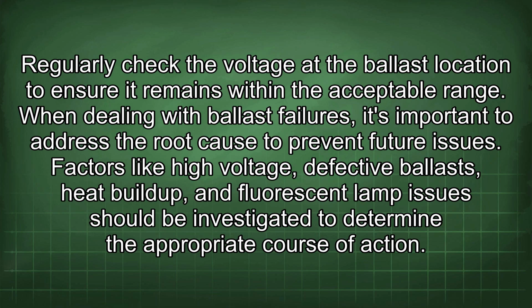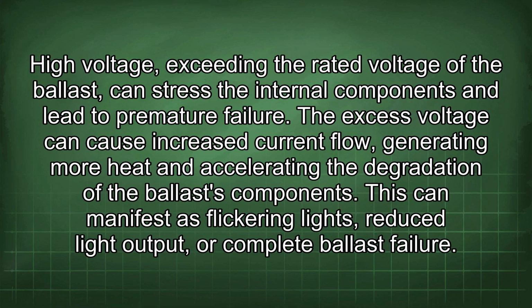When dealing with ballast failures, it's important to address the root cause to prevent future issues. Factors like high voltage, defective ballasts, heat buildup, and fluorescent lamp issues should be investigated to determine the appropriate course of action. High voltage, exceeding the rated voltage of the ballast, can stress the internal components and lead to premature failure. The excess voltage can cause increased current flow, generating more heat and accelerating the degradation of the ballast components. This can manifest as flickering lights, reduced light output, or complete ballast failure.